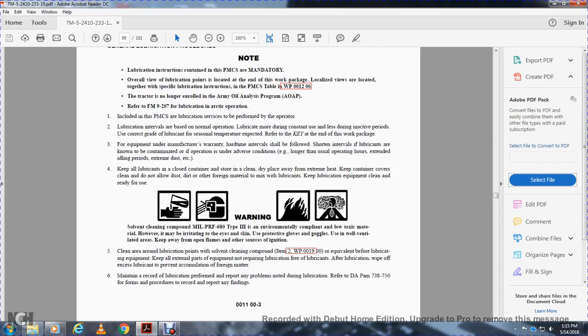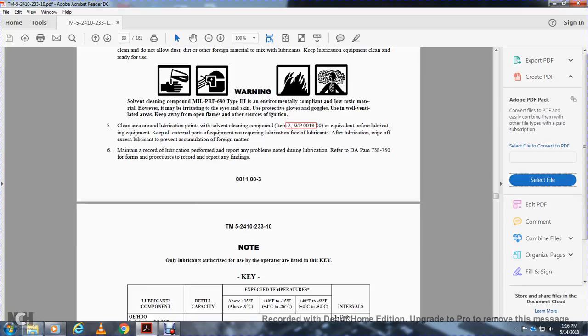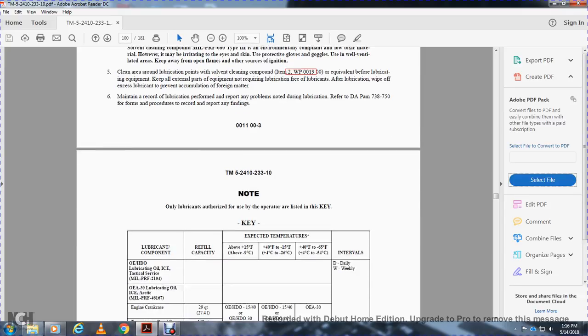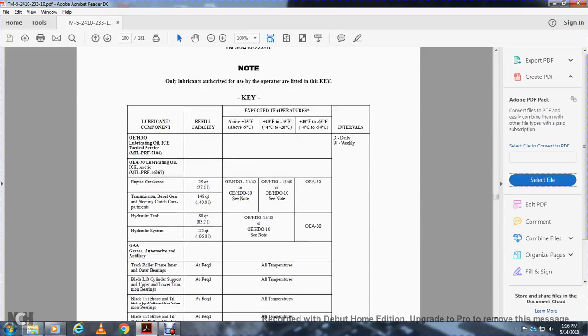Clean the area around the lubricating points with a solvent cleaning compound or equivalent before lubricating the equipment. Keep all external parts of the equipment not requiring lubrication free of lubricant. After lubricating, wipe off excess lubricant to prevent accumulation of foreign material. Maintain a record of lubricating performance and report any problems during lubrication. Refer to DA Pam 738-750 for forms and procedures to record and report any findings. Only the lubricants used by the operator are listed in this key.